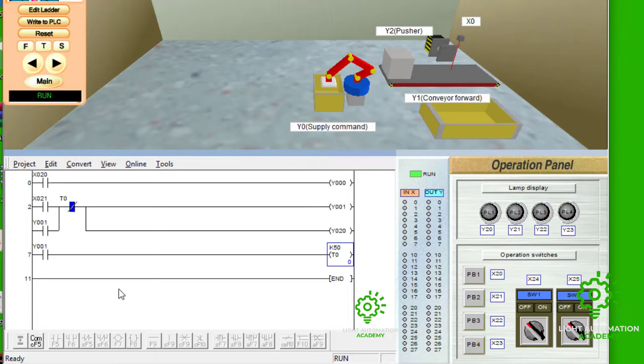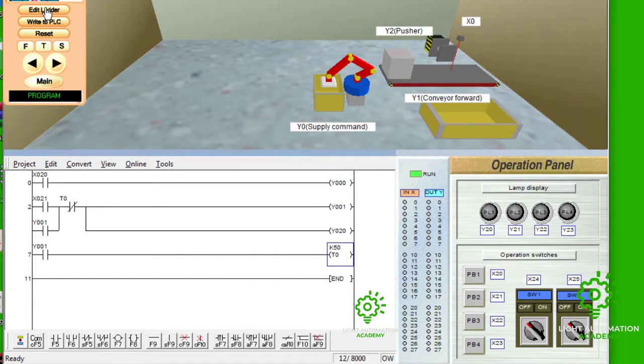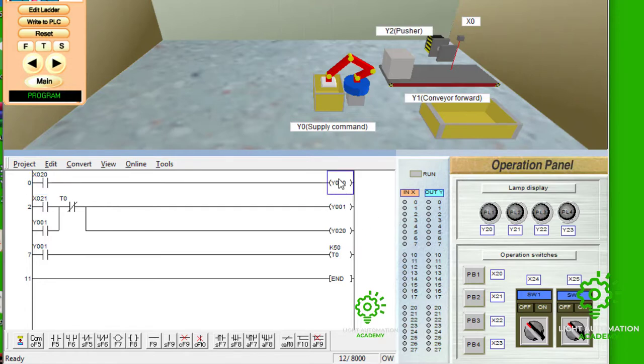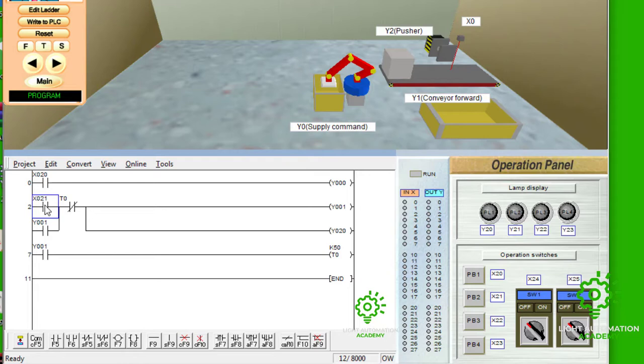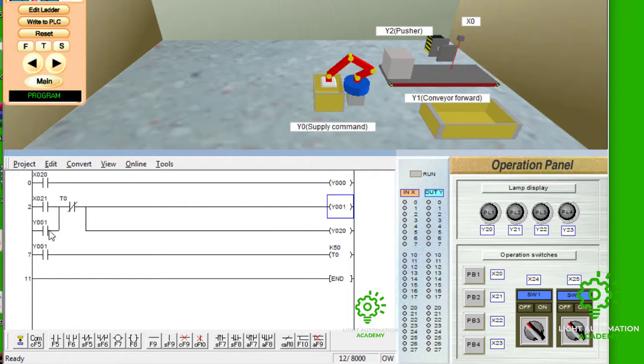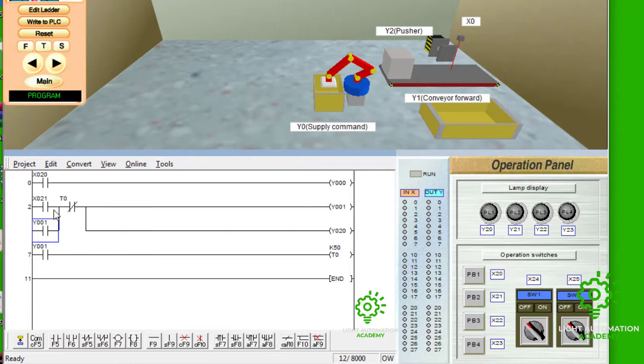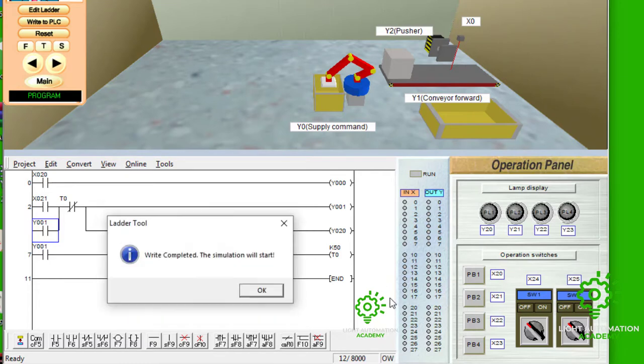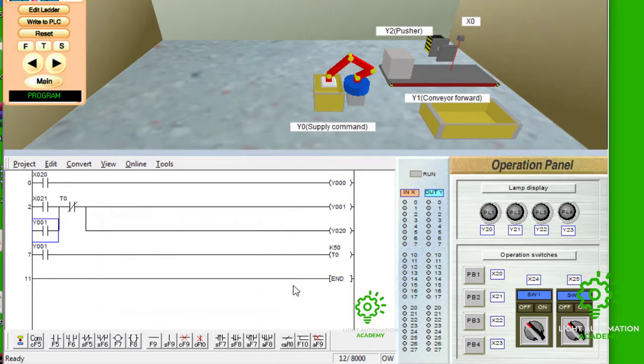Now, we're going to be explaining again. Normally, in the other class we have, we said X20 is an input. Y0 is an output. Then we are using an input to supply power to an output. Then we use a switch to on our conveyor, which is Y1. But now, we want to be able to use a push button to act like a switch. So, we put the address of our push button here and the output of our conveyor, which is Y1. Then, we put an open branch from here with the same address of our conveyor. Then, we send the power to it. Then, our push button is working like a switch. So, you don't need to continually press it.